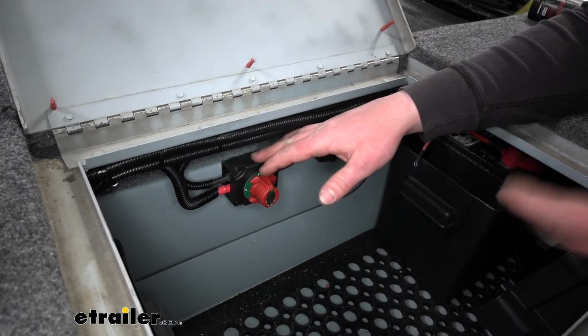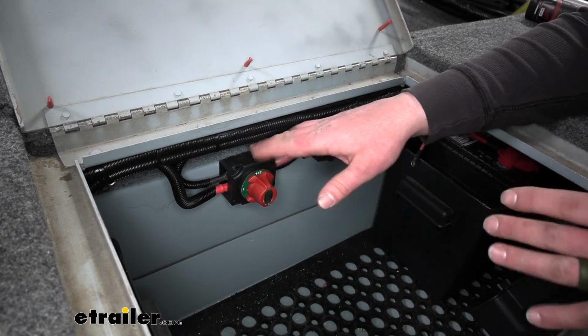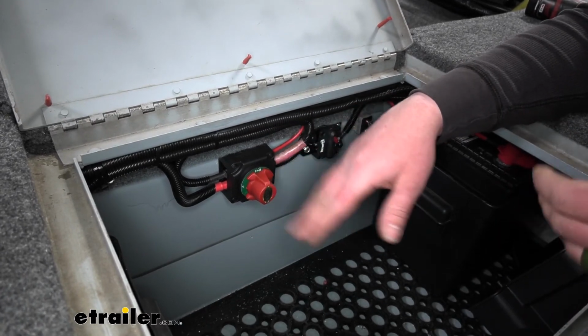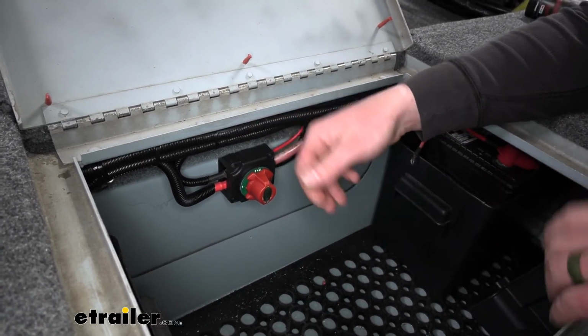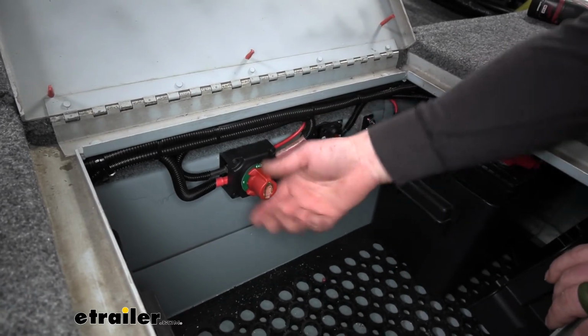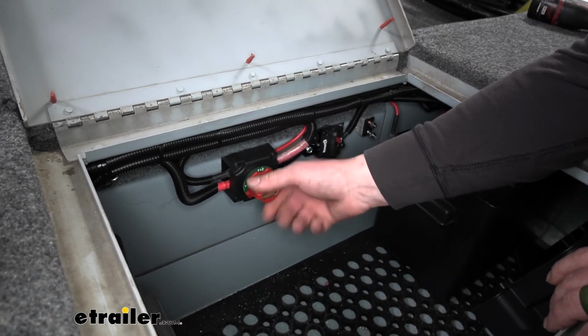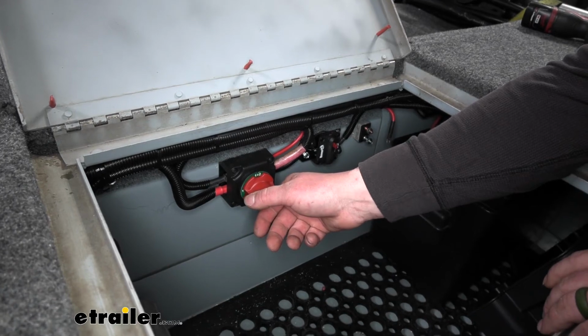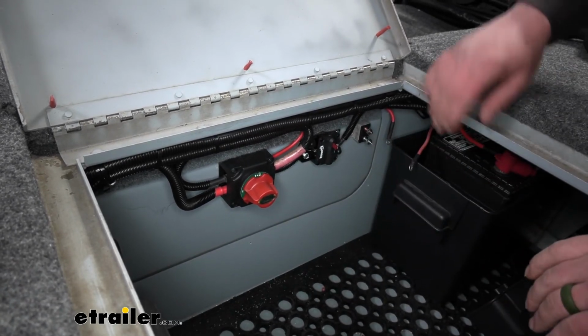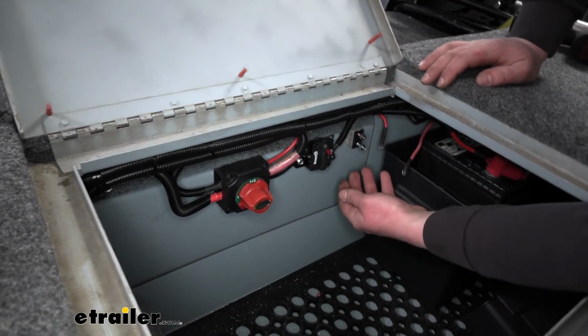Before we get anything hooked up, we want to make sure our power source is off. Either disconnect your batteries, or in our case we have a disconnect here, so I'll put that into the off position. Now that we have no power, we can get our wires hooked up to the breaker.